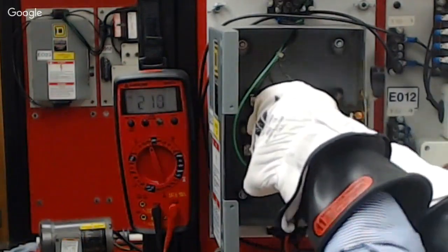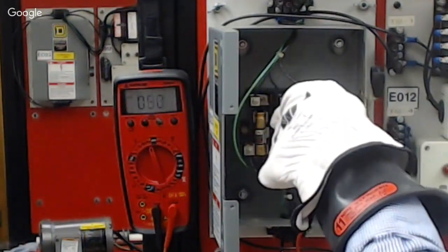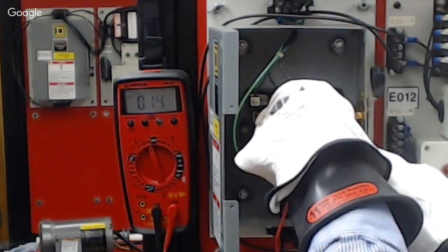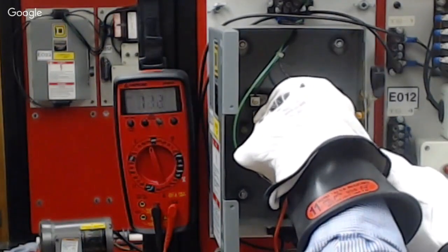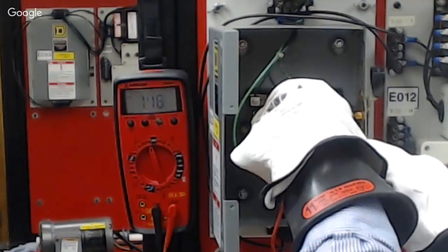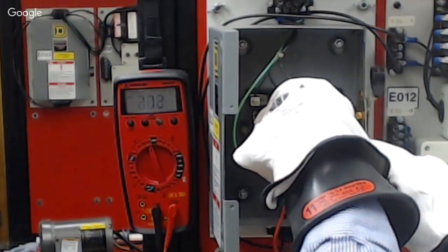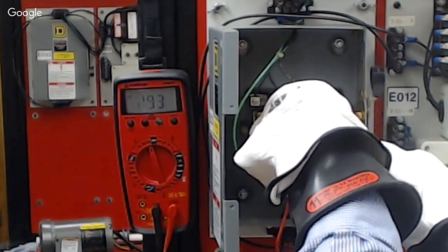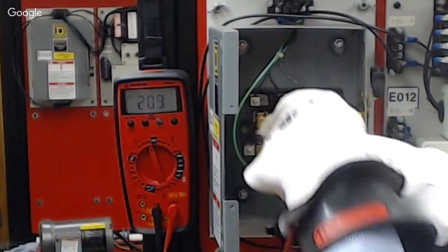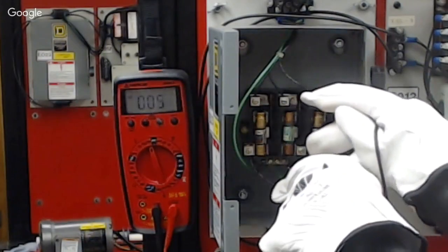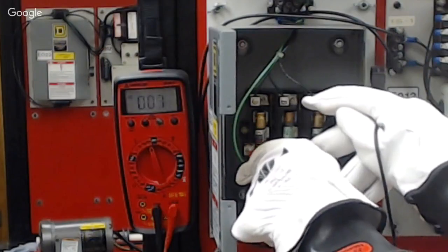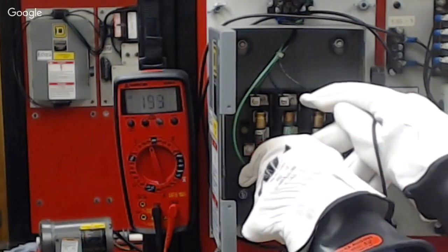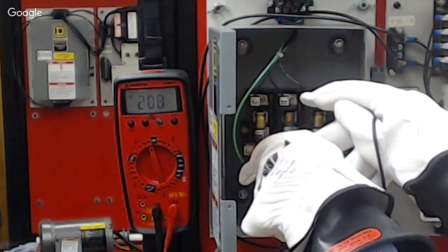I'm going to shift to the source side of L2 and check to the bottom. We're checking the L3 fuse now. And so I'm going to check here, and I should be reading 208. Now I'm going to switch. So I'm going to go to the source side of L3 and check to the bottom side of L1, and I should be reading 208. That tells me all these fuses are good.